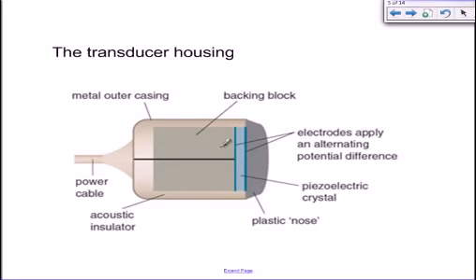The transducer is here, this little blue strip here, and it's placed inside a housing, which includes some acoustic insulators to stop the signal. What we don't want is the signals coming back this way because the body is over here. So we have to prevent any vibration of the housing. And that's done by this backing block, which is an acoustic insulator, as well as the casing around it. So there are no vibrations from the operator's hand, for example, or from the air around, which will affect the signal. The nose of the transducer housing here is plastic, and it acts as a bit of an acoustic lens to focus the ultrasound pulses into the body.